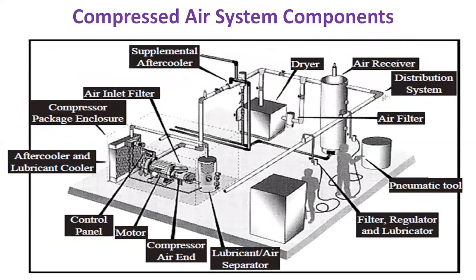Apart from the compressor itself, several system components must be understood. Air intake filters prevent dust from entering the compressor and are specified in microns — a 5-micron filter stops particles above 5 microns but not below. Interstage coolers are required during multi-stage compression because temperature rises at each stage; they are mostly water-cooled and need maintenance per manufacturer recommendations.